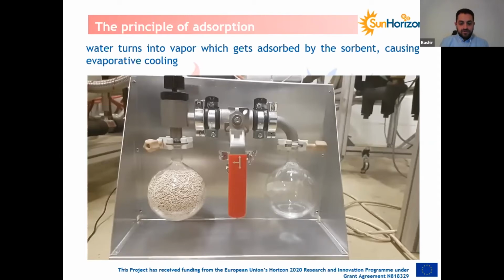Both containers are under vacuum. In the demonstrator, when we open the loop between the two glass containers, the zeolite will attract the water vapor and adsorb it. Under vacuum, the water will evaporate at low temperatures, creating the cooling and chilling effect.